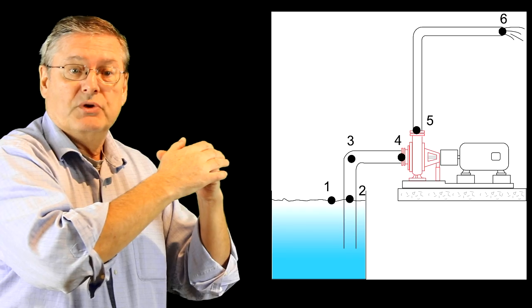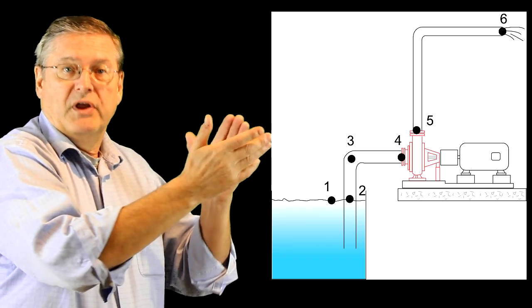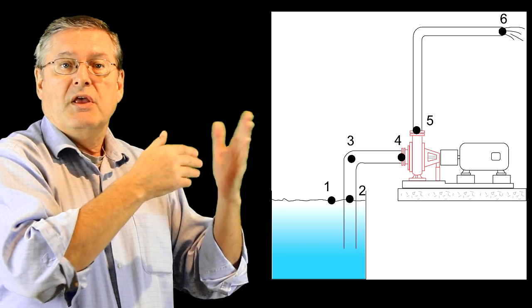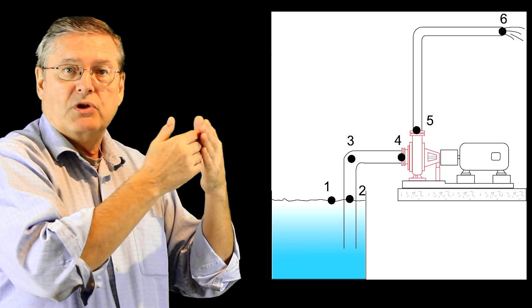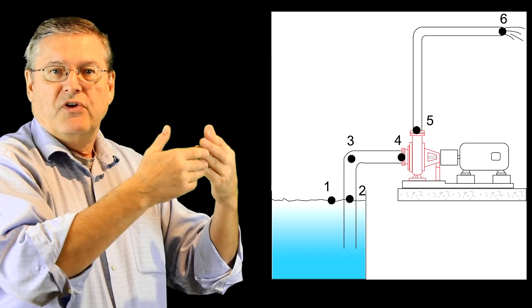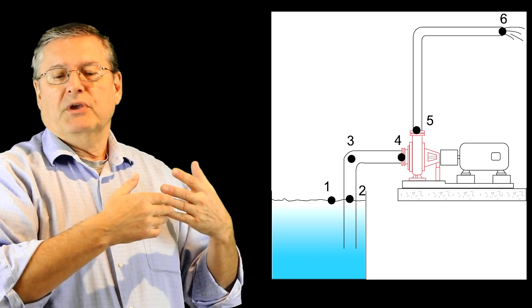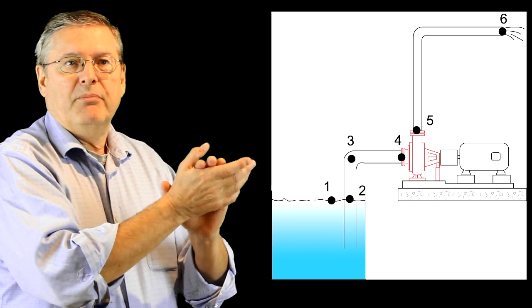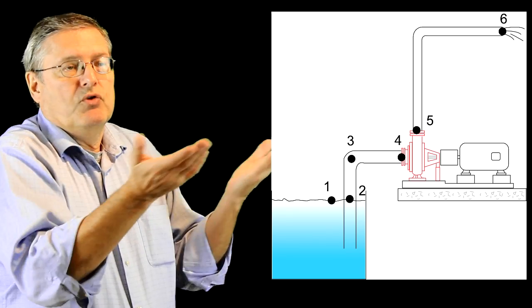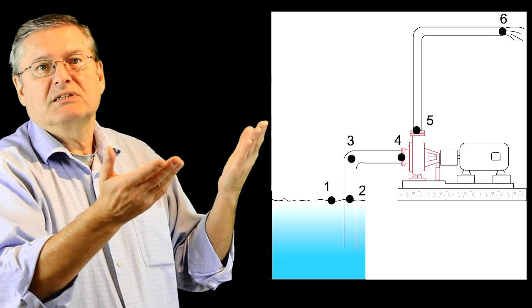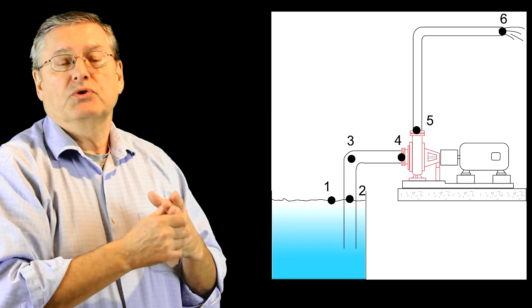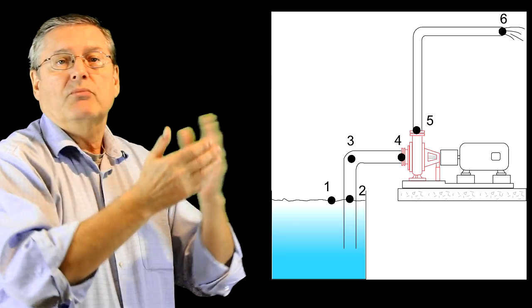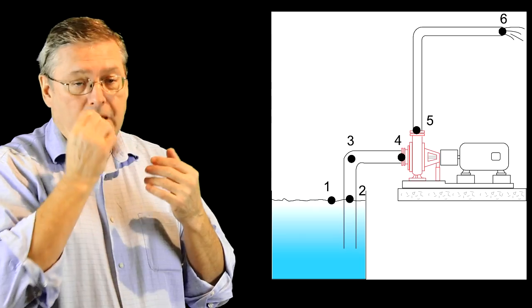As we go up in height pressure drops, and we'll probably be below atmospheric pressure at that point. Point four is the pump entrance — same pressure level as point three minus a little friction. Point five is the pressure increase from the pump. Point six is the pipe outlet going to atmosphere, so at six we have zero pressure. Between five and six we've gone up, lost pressure due to friction, and reached zero at atmosphere.